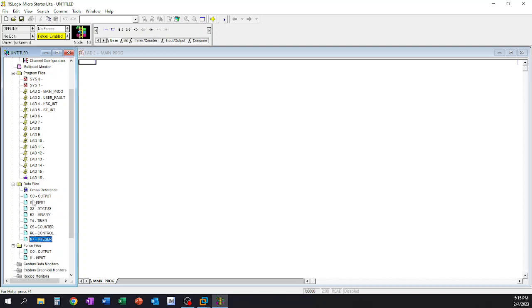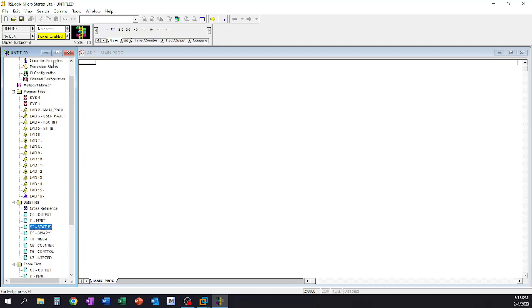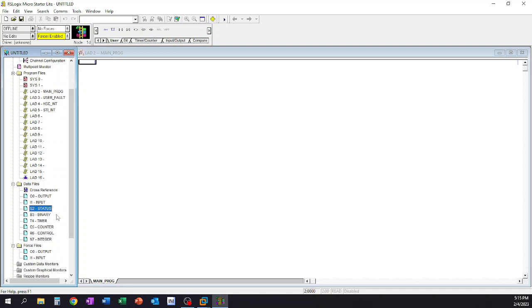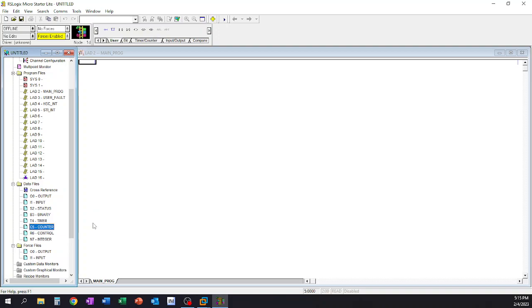So let me quickly walk through this. So O0 or outputs. Those are going to be all your outputs from your controller. I1, those are your inputs. Those are anything that's a physical input. Status is your controller or processor status. So we just went ahead and talked about here a little bit ago. B3 is your binary. So that's your Boolean bits. So it's either on or off. Timers are your T4. So anything that's a timer retentive, timer on, timer off, those kinds of things are always going to be your timer bits. Counters, count up, count down. Those are your timers or excuse me, counters. And then R6 control that's generally used in a sequencing function. So when we step positions through sequencer, that'll be in the R6 control. And then N7 is your integer. So exactly like it would be in Studio 5000. It's an integer, double integer, and then single integer file, the same process there as well.